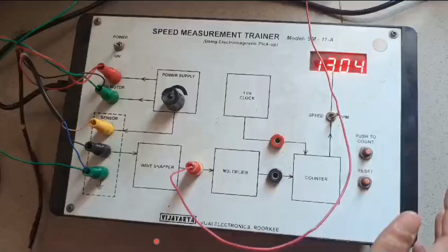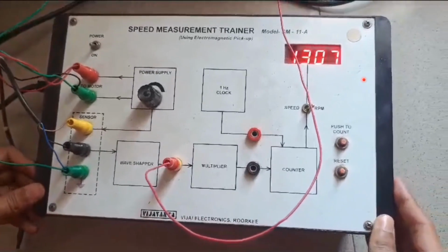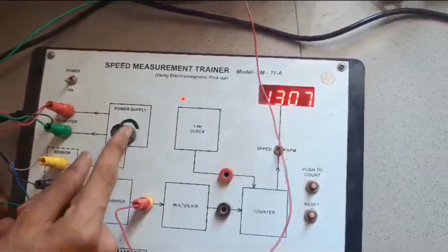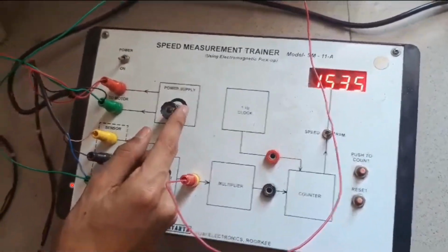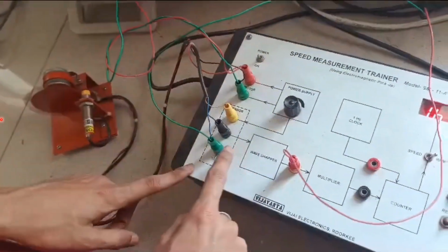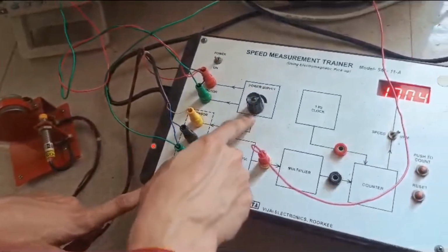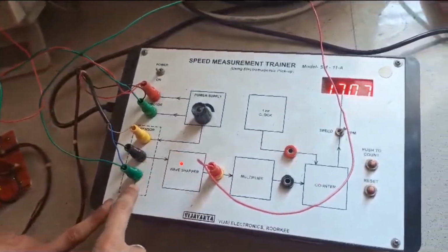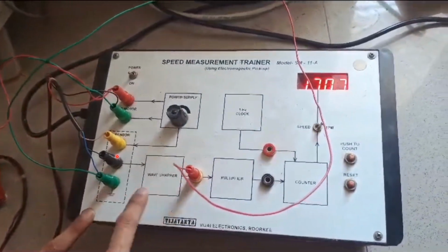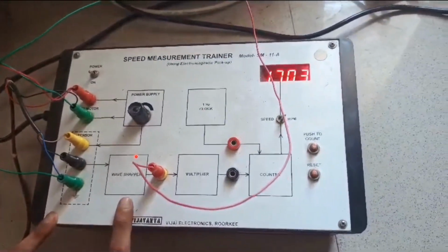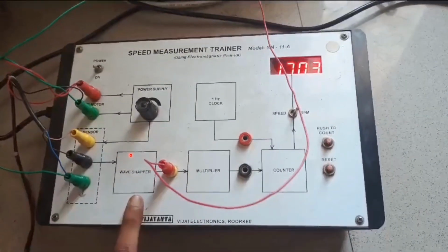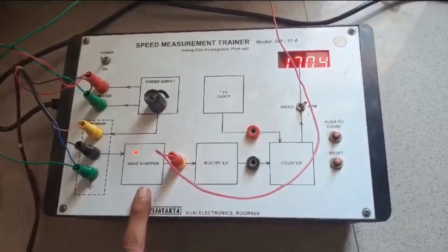So basically, this is the excitation source. We rotate the knob to increase the speed, increasing the value that is coming here. This rotational power supply is then sent to the sensor. One is grounded, one is connected with the shaft, and one is connected to the wave shaper. Now, what the wave shaper does is reduce the unwanted AC signals sensed by the MPU sensors.